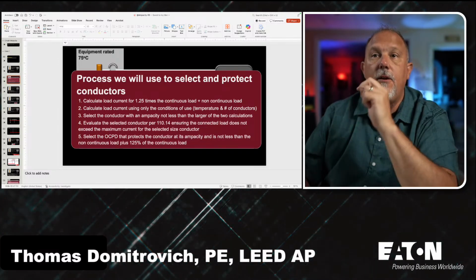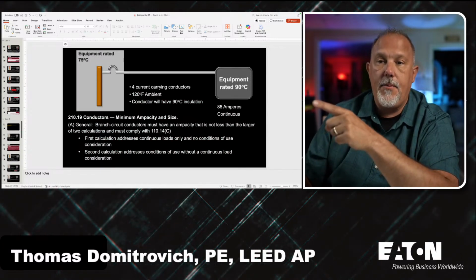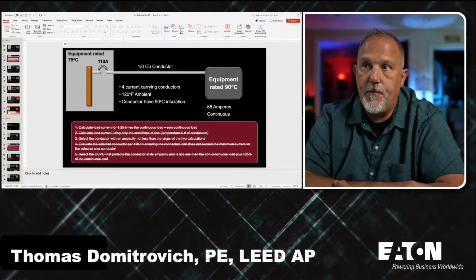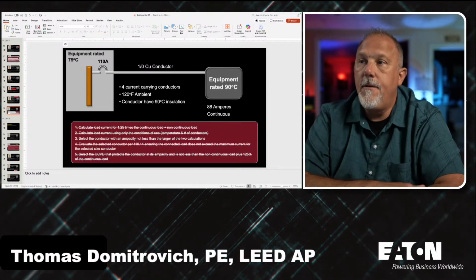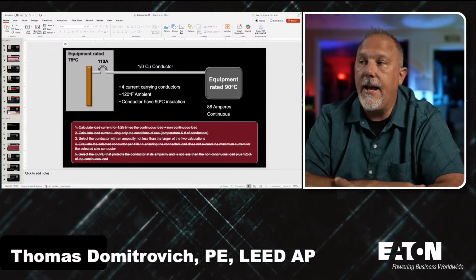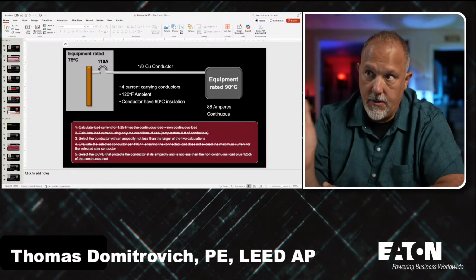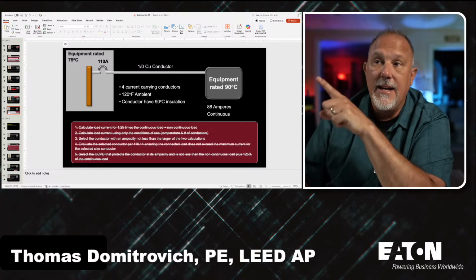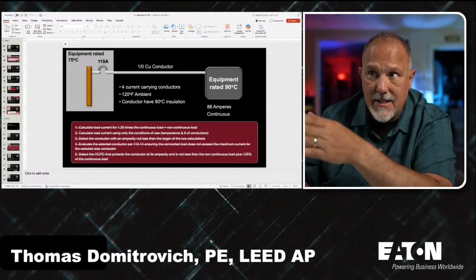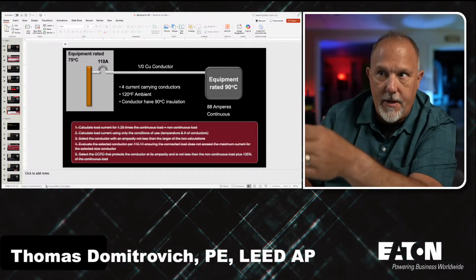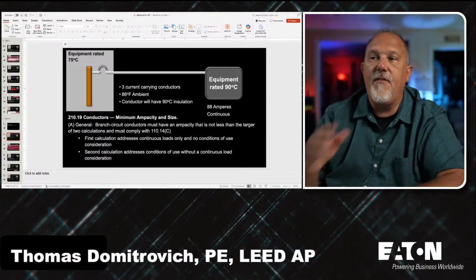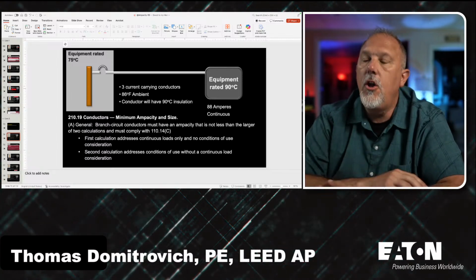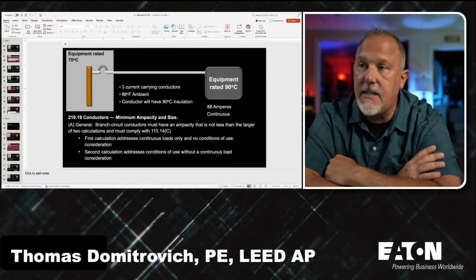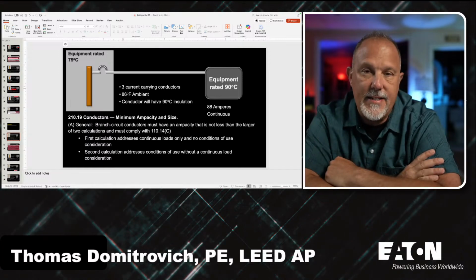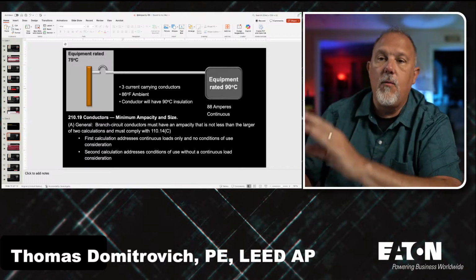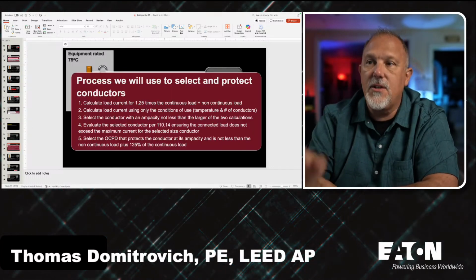We're developing our PowerPoint. So remember, this situation ended up with a 1-aught copper conductor with a 110 amp circuit breaker feeding a load that had 88 amps of continuous current. Okay, that's where we ended up. So now we're going to take this not exact same layout, the same size conductor, the same load, the same equipment, but we're going to specify that we have 3 current carrying conductors, not 4 or more. We are in a reasonable ambient of 86 degrees Fahrenheit, and we have the same 90 degrees C insulation. And we're going to apply our process of calculating the load.